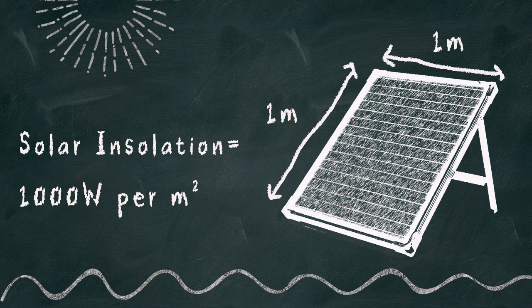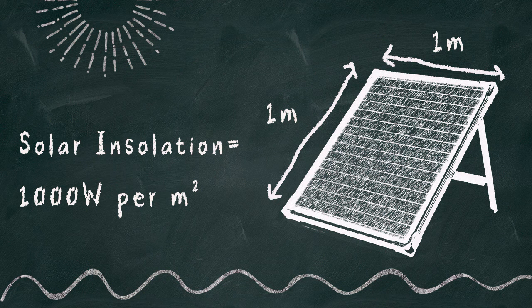The test value known as solar insolation is 1,000 watts per square meter. If you had a 1 square meter solar panel that operated at 100% efficiency, it would generate 1,000 watts. Most electric solar panels operate in a range of 15 to 20%, and that would generate 150 watts to 200 watts. Solar thermal panels in the 85% range would generate heat equivalent to 850 watts of power from an electric heater.